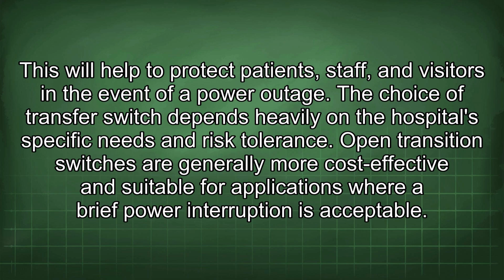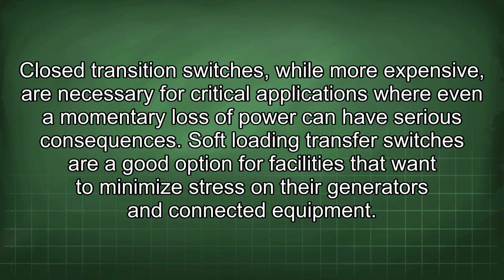The choice of transfer switch depends heavily on the hospital's specific needs and risk tolerance. Open transition switches are generally more cost-effective and suitable for applications where a brief power interruption is acceptable. Closed transition switches, while more expensive, are necessary for critical applications where even a momentary loss of power can have serious consequences. Soft-loading transfer switches are a good option for facilities that want to minimize stress on their generators and connected equipment.